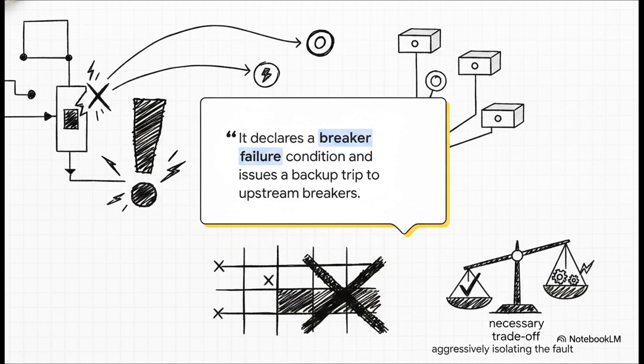Now, the severe consequence of this action is that it widens your outage footprint. You're aggressively isolating the fault by taking out way more of the grid than you originally intended. But it's an absolutely necessary trade-off to stop the ongoing destruction.